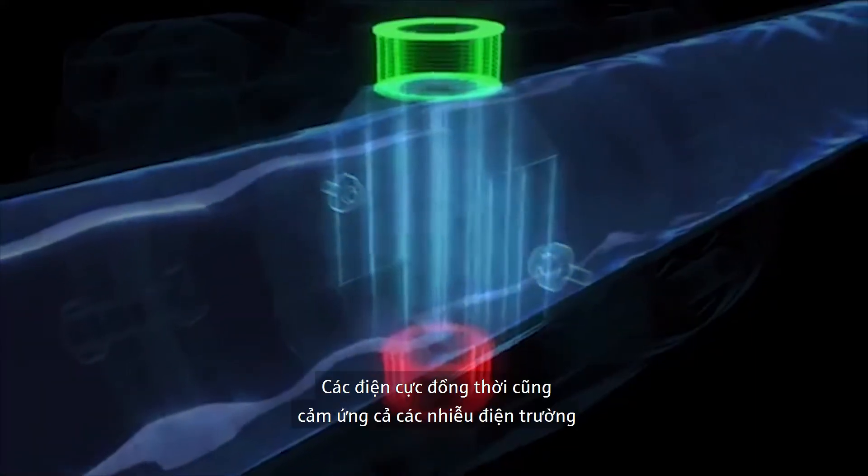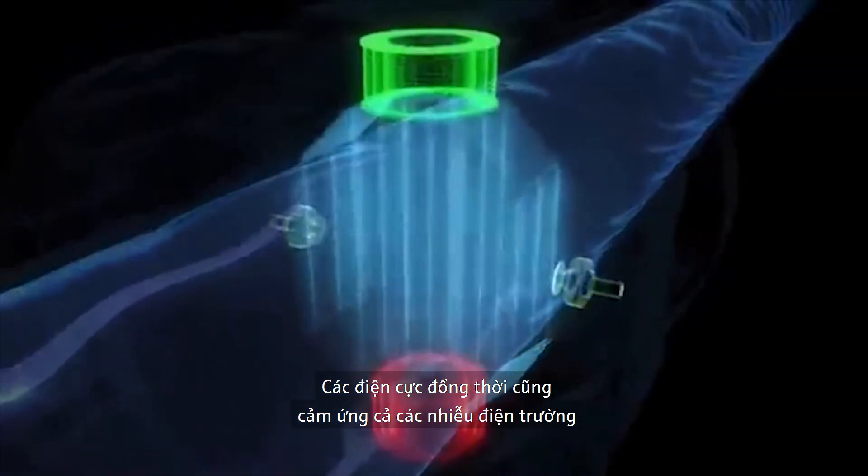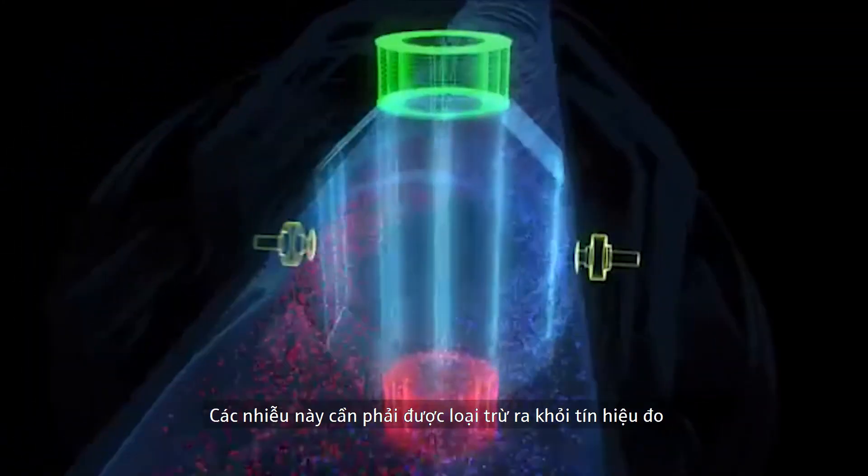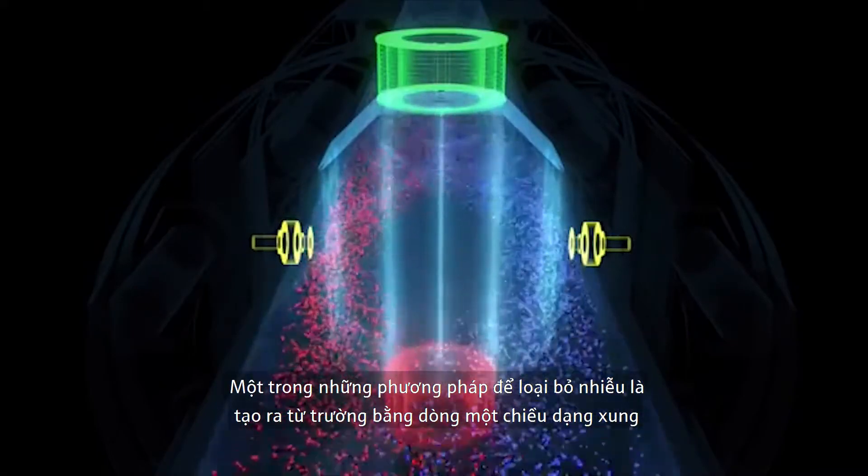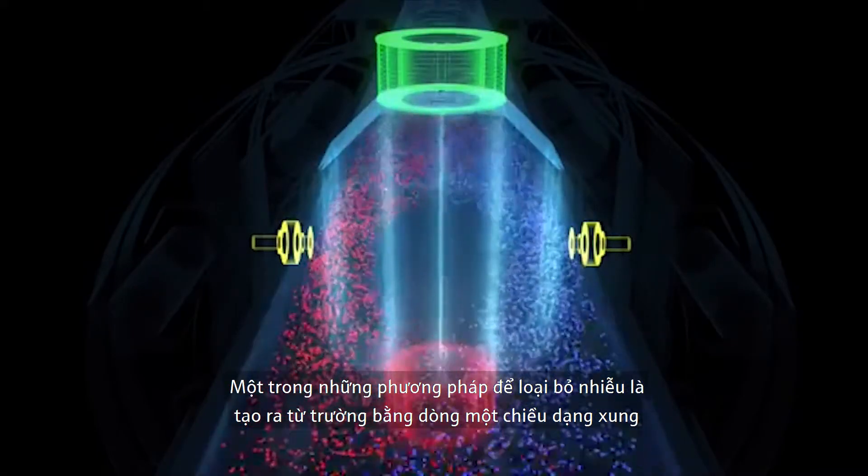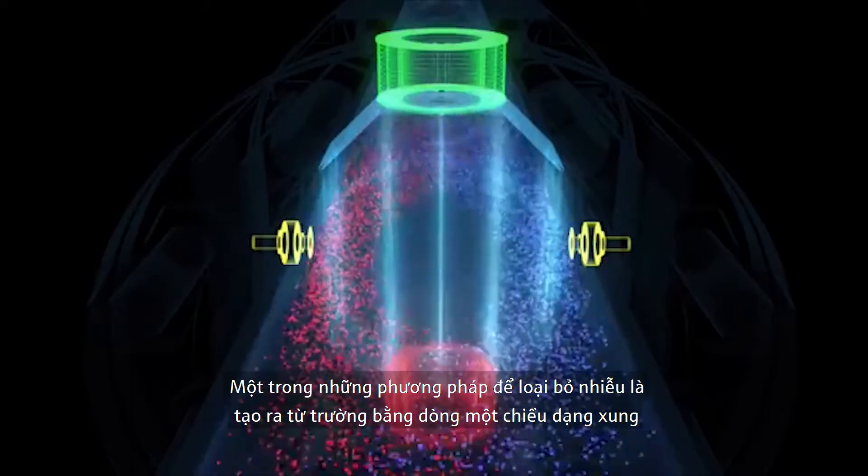The electrodes also detect what is called interference voltage, which has to be separated from the actual measuring signal. One method that has been successfully used for this purpose is to create the magnetic field with a pulsed direct current.